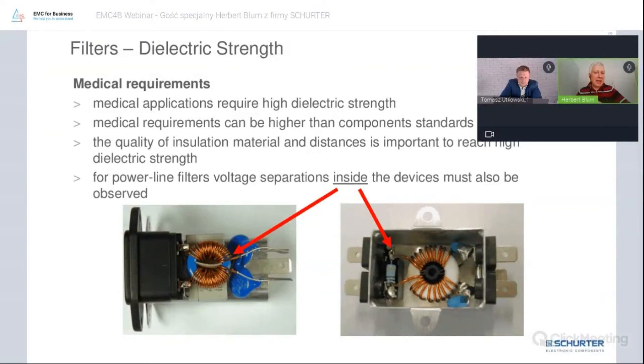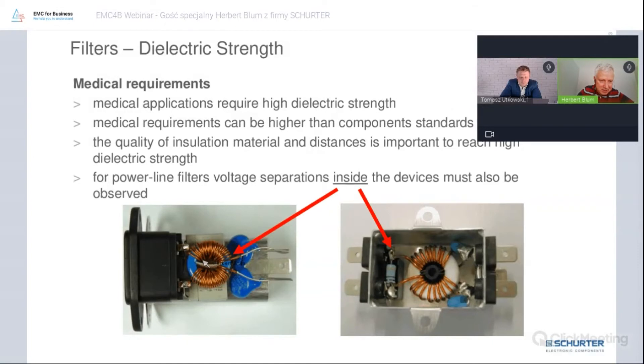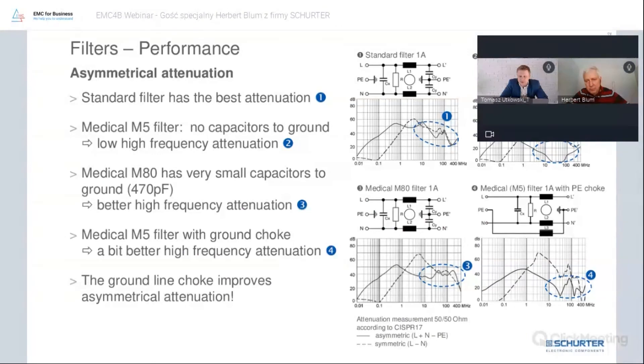That is sometimes a problem because, as you can imagine, if the neutral line is here and I need three millimeters of clearance distance — that is not always easy to achieve.